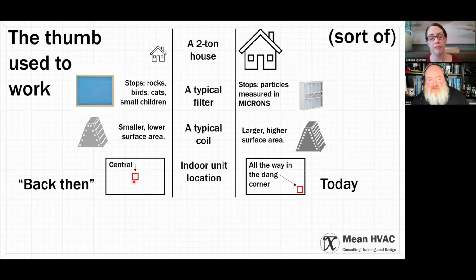Once upon a time, they used to put the unit in the middle of the house. It's called central air, not corner air. When the unit is in the middle of the house, you cut the distance from the furthest point in half, and it's really good for the blower to do an easy job of air delivery. Stick it in the corner, and getting all the way across the house is a really difficult job for the blower. You need to compensate for that by making ducts bigger or doing something other than the way you've always done things, and that's what we're dealing with a lot of the time.